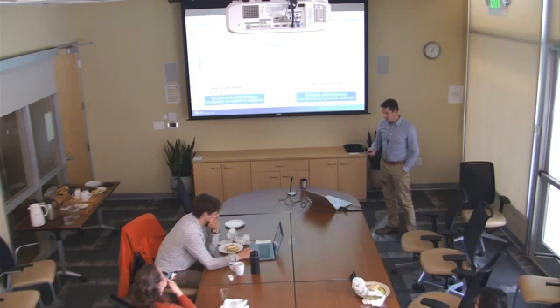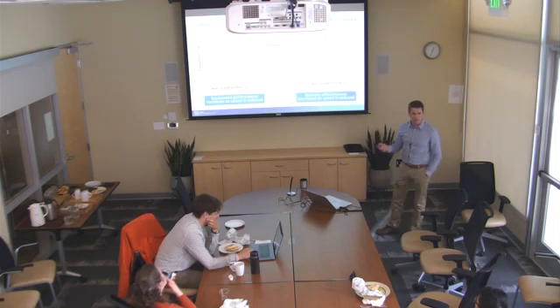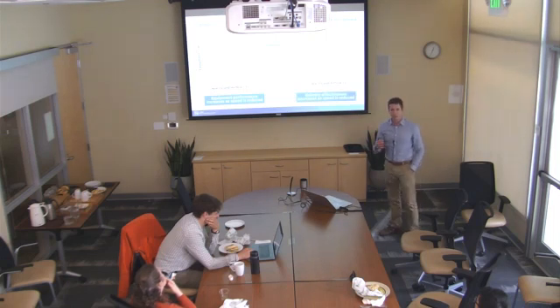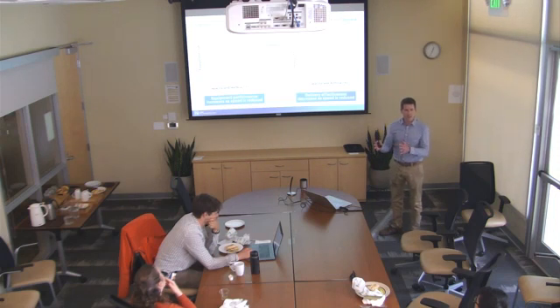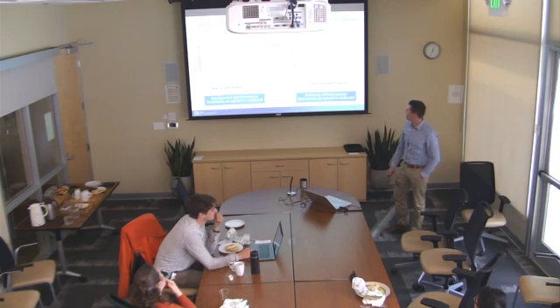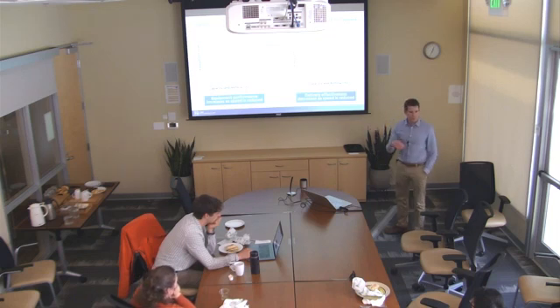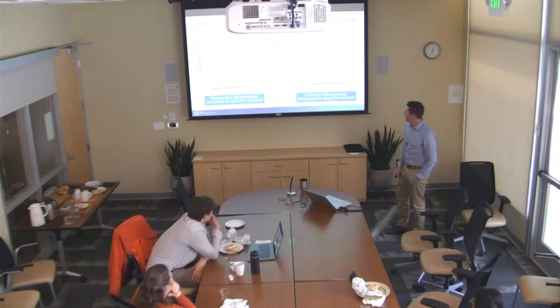Now, when you look at the duct system, we're using a term called delivery effectiveness. This is essentially how much cooling that you're making in your box in the attic actually makes it into the building where you're trying to cool it. So you can see at full speed, you're getting 70 to 80% of your cooling to the space. But as you start to reduce the speed of the equipment, you see some significant losses on the duct side.